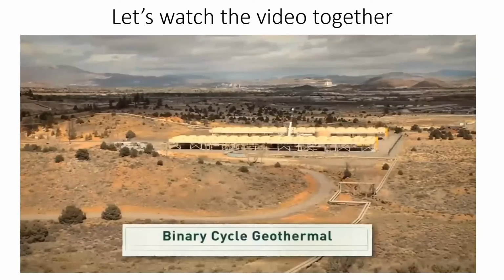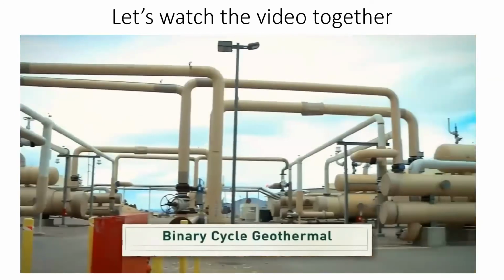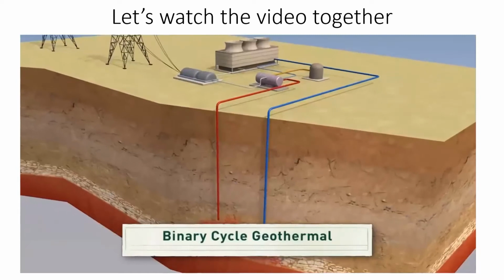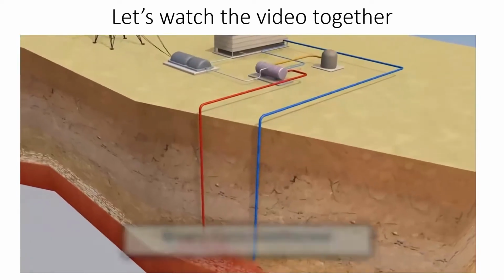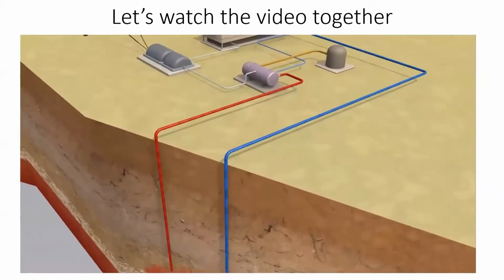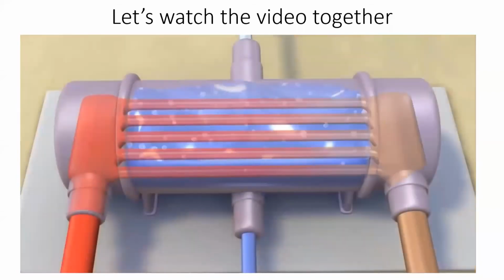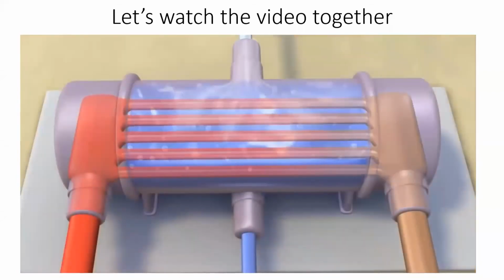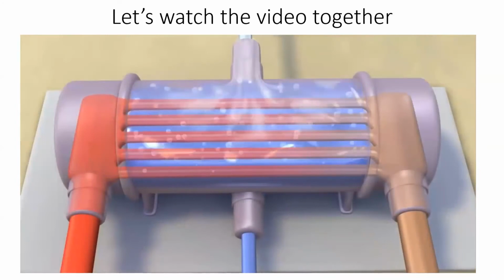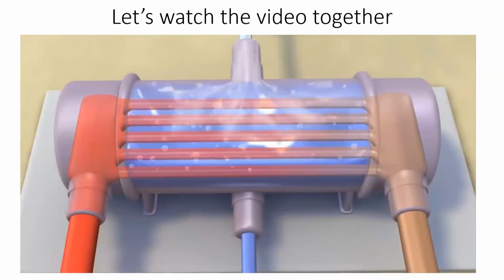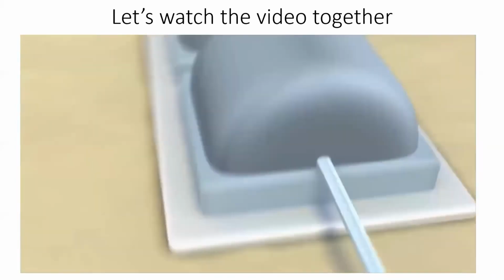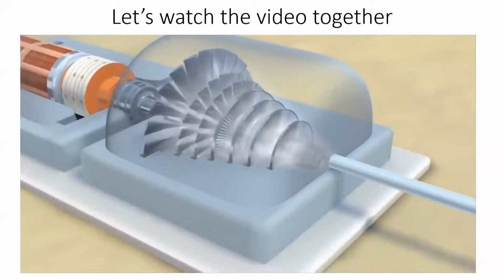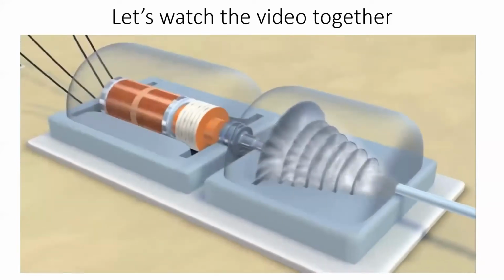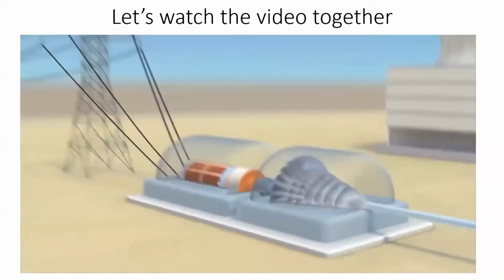A binary cycle plant works differently. It uses two types of fluid. Hot fluid from underground heats fluid, called a heat transfer fluid, in a giant heat exchanger. The second fluid has a much lower boiling point than the first fluid, and so it flashes into vapor at a lower temperature. When the second fluid flashes, it spins a turbine that drives a generator.